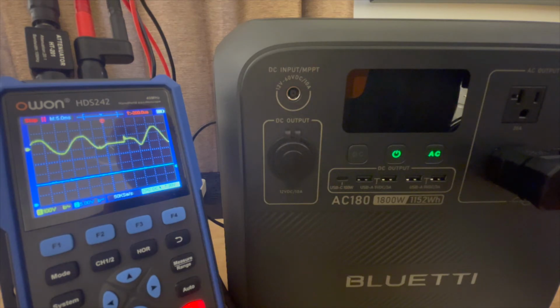The way an offline UPS works is when the power goes out, it very quickly switches to the battery. In other words, the AC input goes straight to the output as long as there are no problems. When it detects a problem, it switches that input from the AC to the inverter, and there is a non-zero switch time. So the first question is, how long is the switch time?